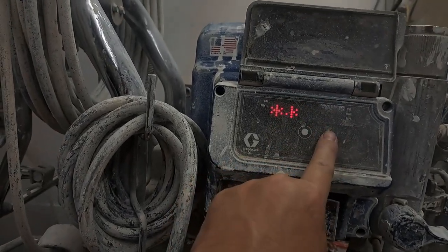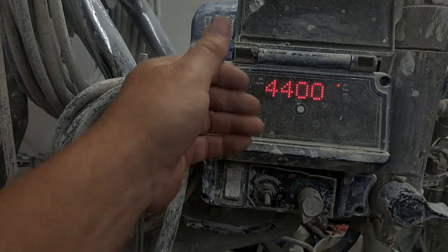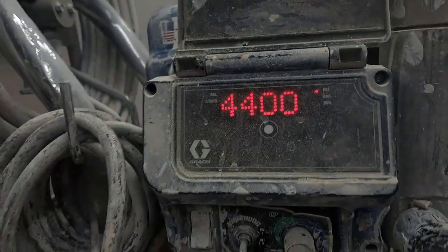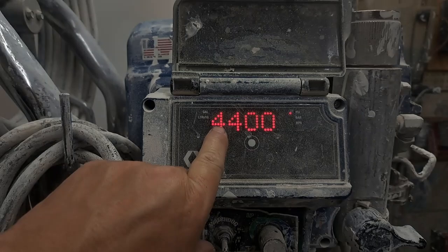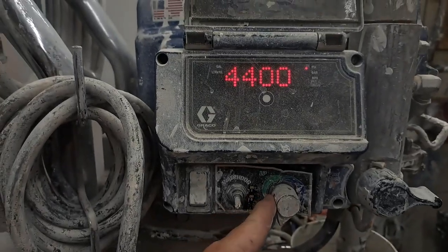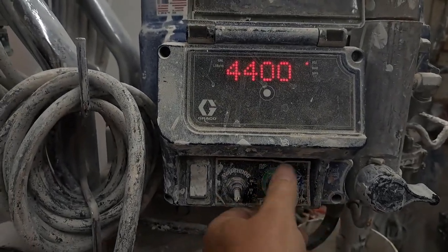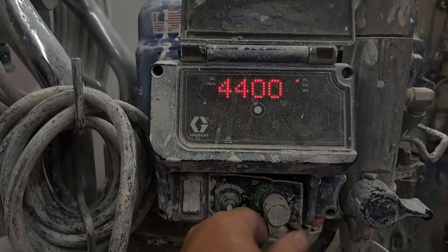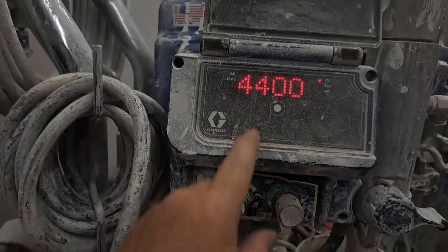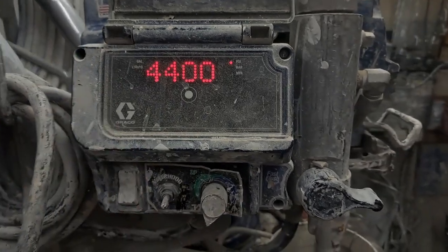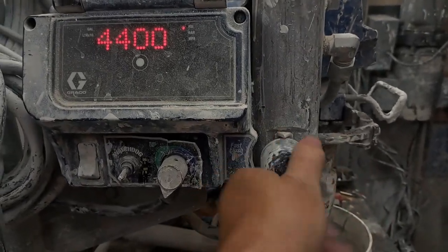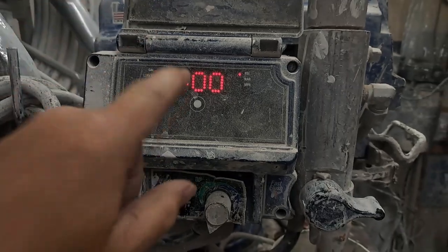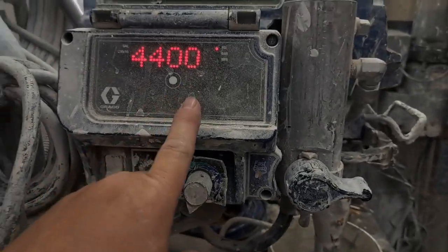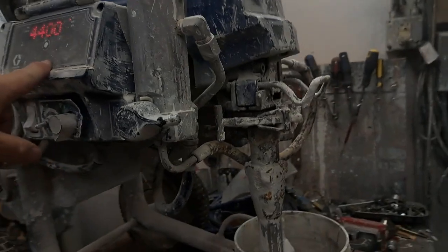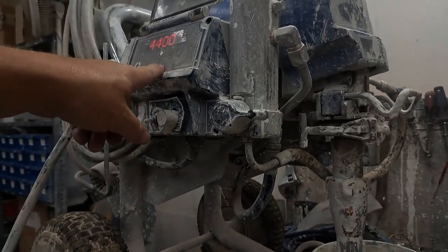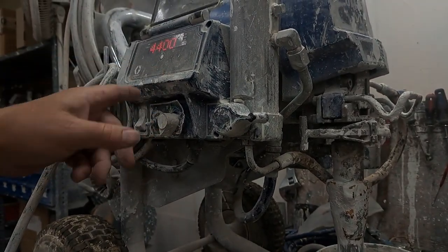And if you don't have a readout, you take the cover off and you're gonna look inside and you'll see a board. But you see it says 4,400 PSI. We're turned all the way down. We're not turned up, we're not turned down. 4,400 is way more than this machine's supposed to produce anyway. So that tells me there's some kind of a pressure issue. There's no pressure on the machine. It's just giving a false reading, and that's due to the transducer, which is common when the transducers go bad. Transducers can go bad just on their own or because they've frozen.